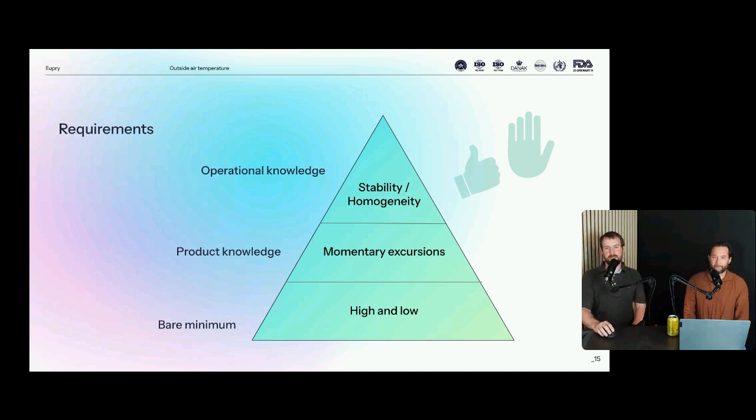Yeah, absolutely. And I was just looking here because we have some interesting questions. Thank you very much. There was a question from Mustafa regarding whether software involved in temperature mapping needs to be validated and how that validation is demonstrated. Thank you very much, Connie, for answering exactly as it is: mapping is a GxP activity, so any software would need to be validated. Spot on. Remember the predicate rule: if you need to make a GxP decision based on something, and it is a GxP required thing to perform mapping, then any software used in that sense needs to be validated. And thank you very much, Connie.